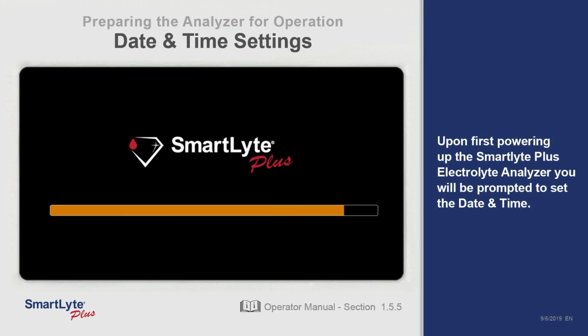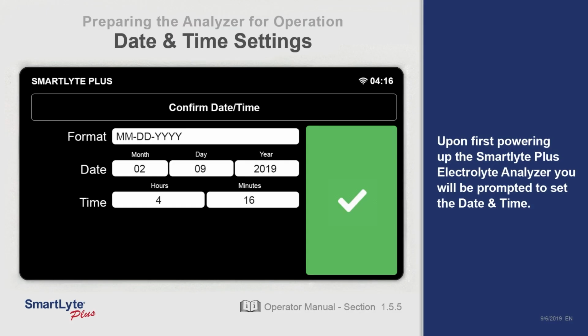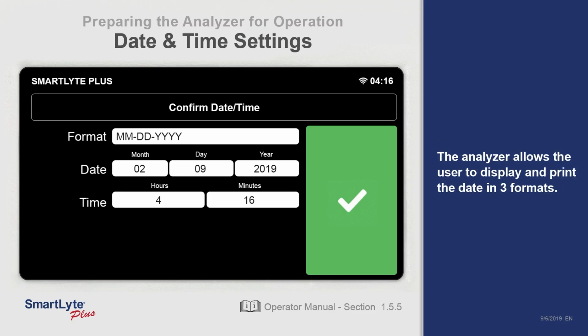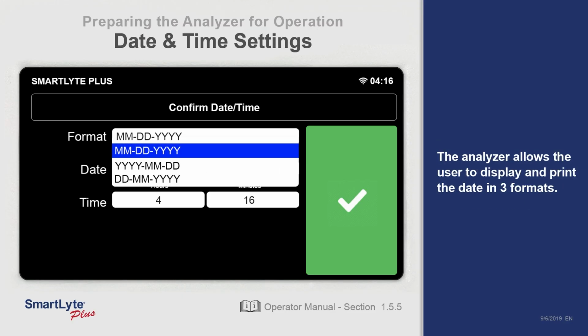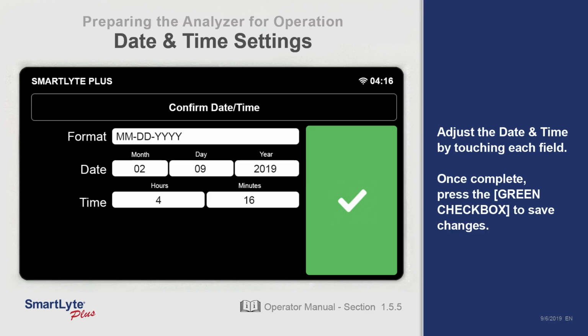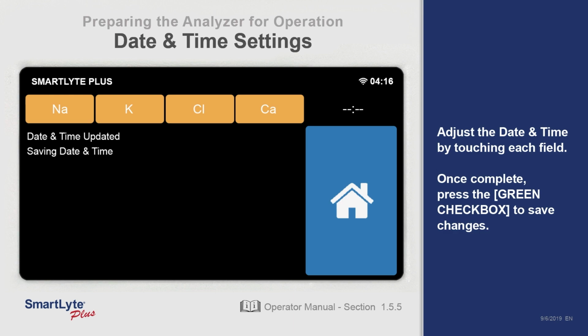Upon first powering up the SmartLyte Plus electrolyte analyzer, you'll be prompted to set the date and time. The analyzer allows users to display and print dates in 3 formats. Adjust the date and time by touching each field. Once complete, press the green checkbox to save changes.